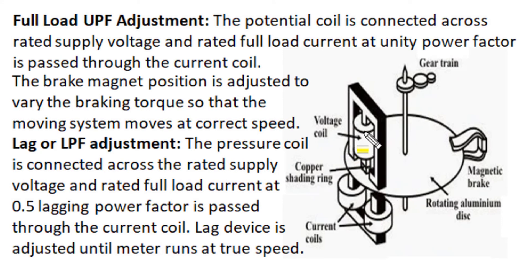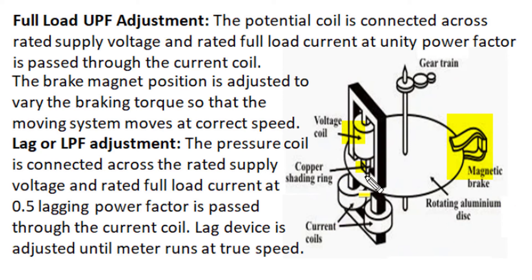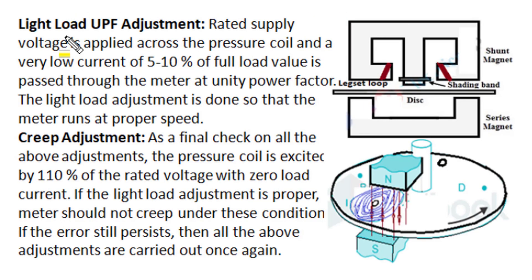After preliminary light load adjustment, full load unity power factor conditions are adjusted. Rated voltage is supplied to the voltage coil and full load current at unity power factor is passed through the current coil. The position of the brake magnet is adjusted to get accuracy in energy meter readings — this is called full load unity power factor adjustment. Next, low power factor adjustment, also called shading band adjustment or lag error correction, is done. Rated voltage and rated current are supplied, but with current lagging voltage by 60 degrees (0.5 lagging power factor), and the position of the copper shading band is adjusted for readings within tolerable error.